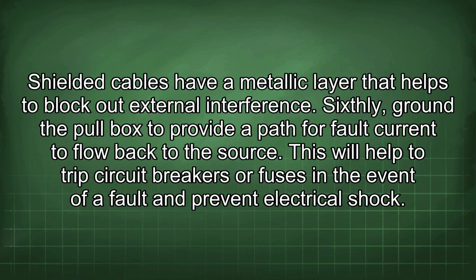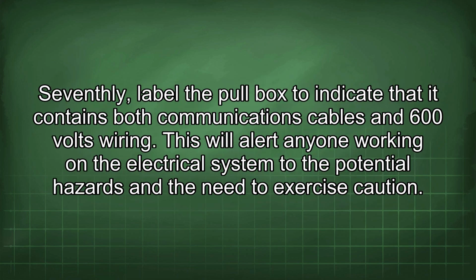Sixthly, ground the pull box to provide a path for fault current to flow back to the source. This will help to trip circuit breakers or fuses in the event of a fault and prevent electrical shock. Seventhly, label the pull box to indicate that it contains both communications cables and 600 volts wiring. This will alert anyone working on the electrical system to the potential hazards and the need to exercise caution.